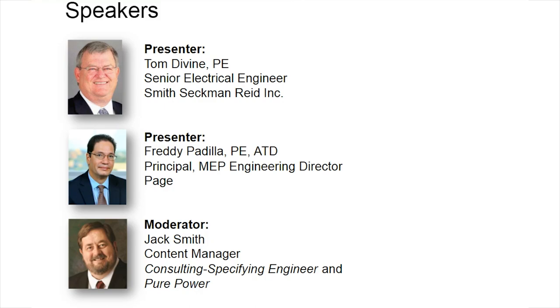The changes to the NEC 2017, we went through a list of those. I can see that I actually did miss the 700.3(F), which requires that I have a permanent method of connecting a temporary generator to serve standby power in the event that something bad happened to my permanently mounted generator.